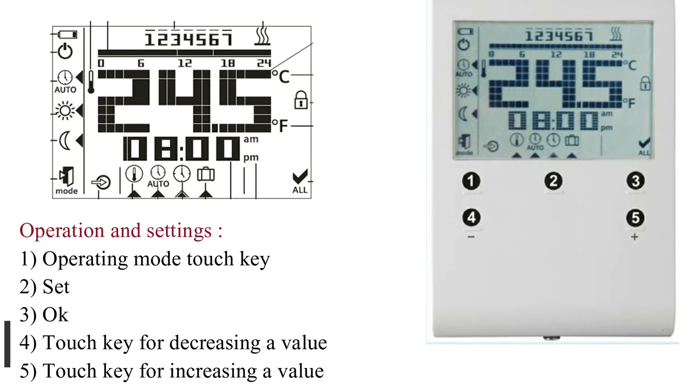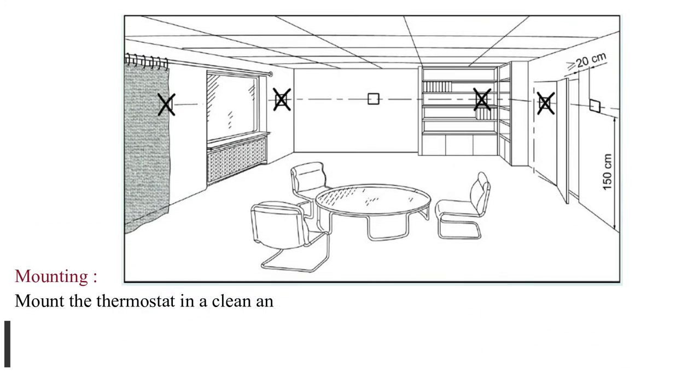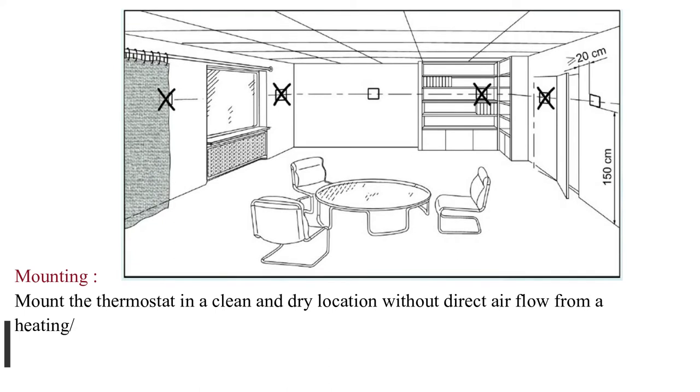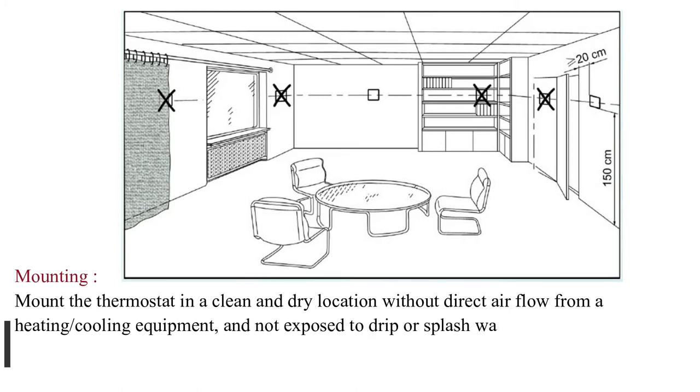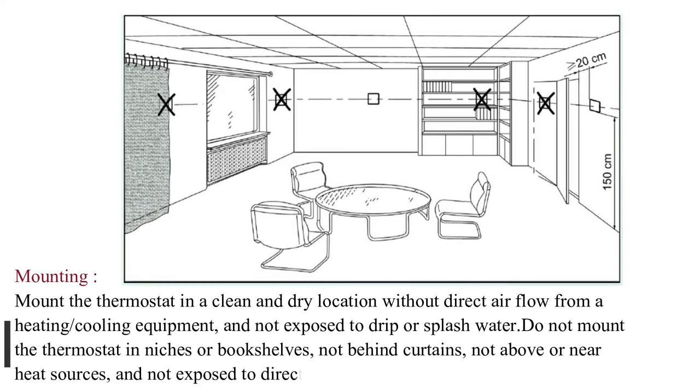Mounting: Mount the thermostat in a clean and dry location without direct airflow from heating or cooling equipment, and not exposed to drip or splash water. Do not mount in niches or bookshelves, not behind curtains, not above or near heat sources, and not exposed to direct solar radiation. Mount about 1.5 meters above the floor.